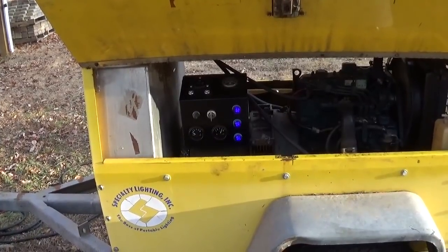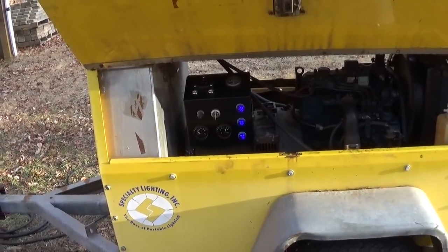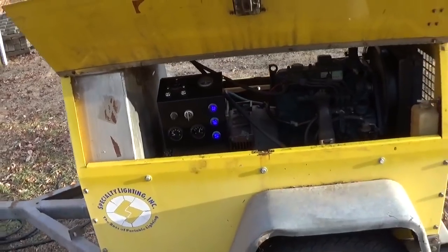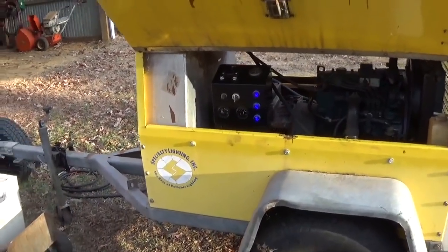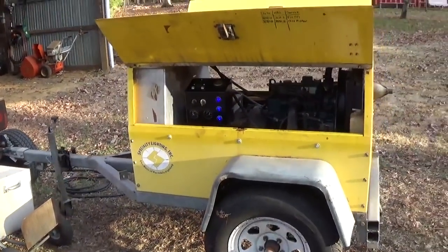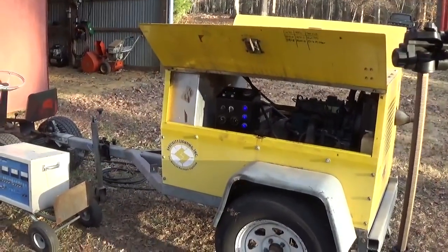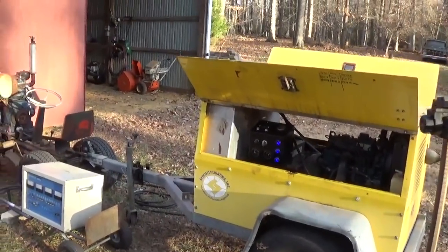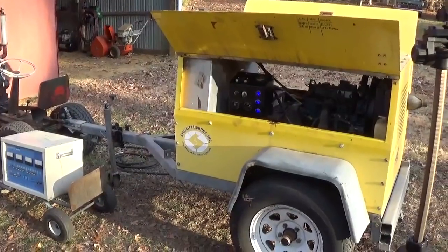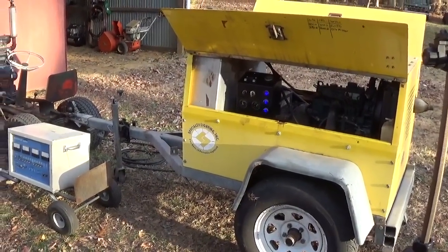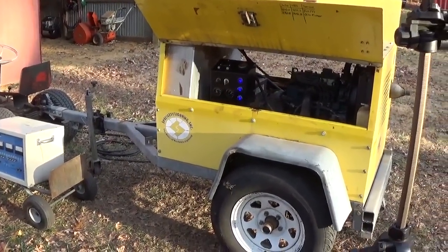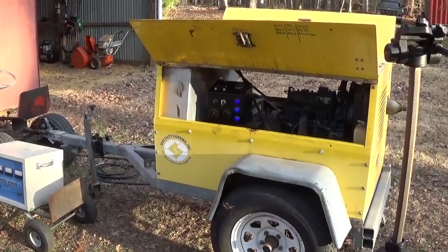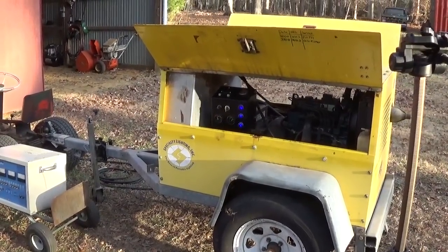I've noticed something showing on that one meter. I think it's because the wiring for the CTs on those little meters might be too close to the load or power wiring, getting a bit of crosstalk or interference between the two. But they are accurate under load.